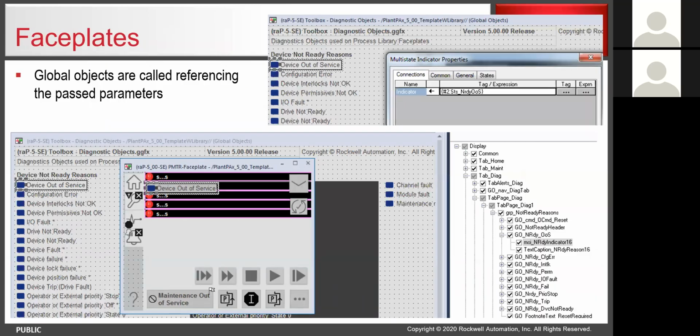So, getting into the faceplates and looking at those specifically, we have a little bit of information on how these things are set up. When you open up one of these faceplates and you look at the Object Explorer, it's a lot of information and stuff stacked on top of itself. In the case of the Rockwell faceplates, there's a macro to change between the different functions, to bounce back and forth between maintenance and other modes. Now, if you're building your own faceplate, you may not include those pieces and you may not need that macro. Typically, most people building their own don't get to that level. You just pop up a more standard, pretty set faceplate where you're more playing with visibility of individual elements and what's going to be displayed, what's going to be interactive, and what isn't.